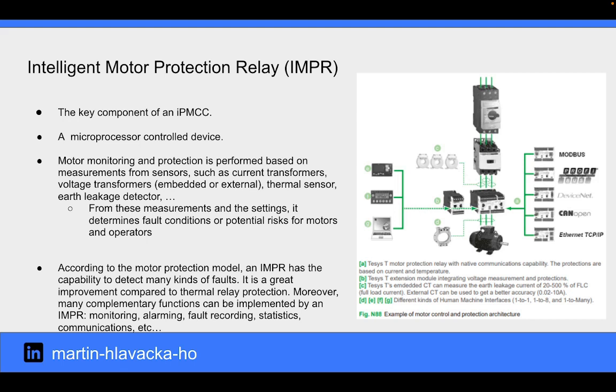Intelligent Motor Protection Relay is the key component of an IPMCC. It is a microprocessor control device. Motor monitoring and protection are performed based on measurements from sensors such as current transformers, voltage transformers, thermal sensors, earth leakage detectors, etc. From these measurements and the settings, it determines fault conditions or potential risks for motors and operators. According to the motor protection model, an IMPR can detect many kinds of faults. It is a great improvement compared to thermal relay protection. Moreover, many complementary functions can be implemented by an IMPR like monitoring, alarming, fault recording, statistics, communications, etc.